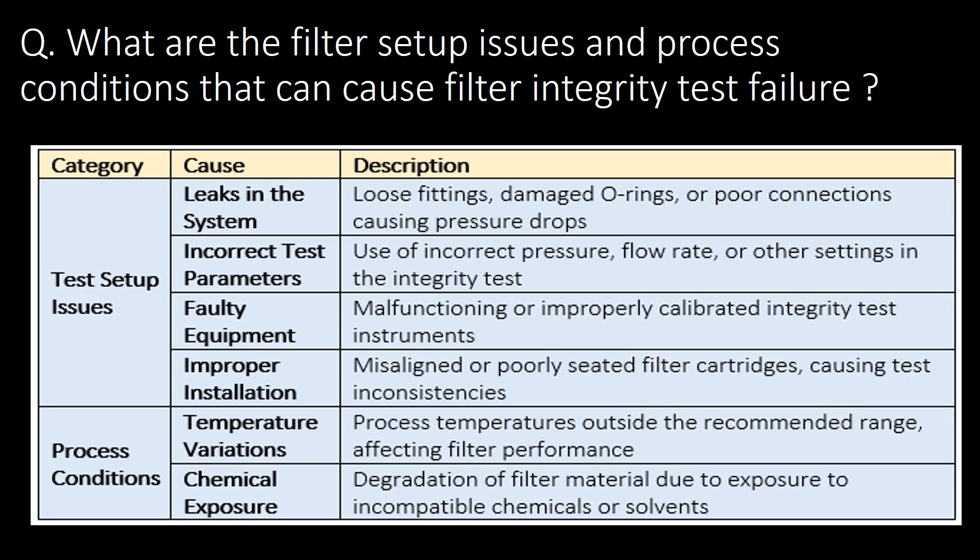What are the filter setup issues and process conditions that can cause filter integrity test failure? Leaks in the system, incorrect test parameters, faulty equipment, and improper installation are the test setup-related issues that can cause filter integrity test failure. Whereas temperature variations and chemical exposure are the process conditions that can cause filter integrity test failure.